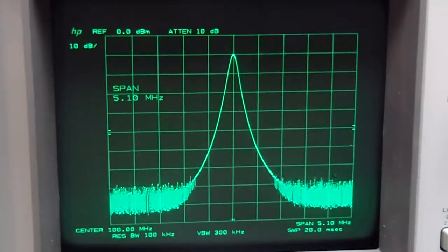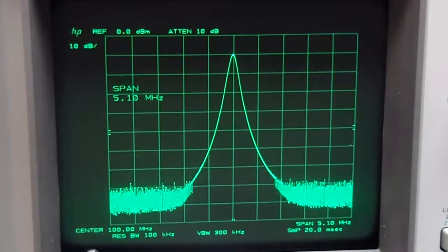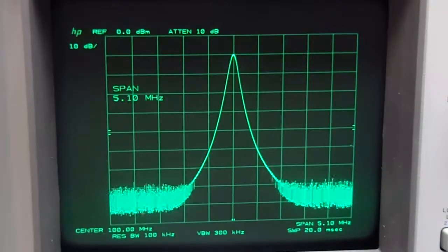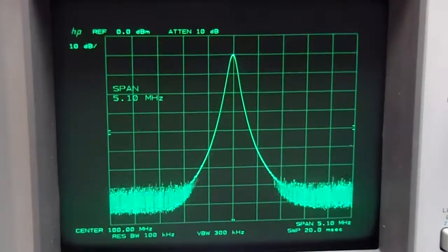So right now what's happening is the spectrum analyzer is locking right here and then rolling the YIG across in an unlocked mode. It goes back and locks and rolls, locks and rolls. So the only part that's synthesized is the very first frequency, and then it's an open loop sweep, and you can actually see the YIG wobble a bit because it is open loop.